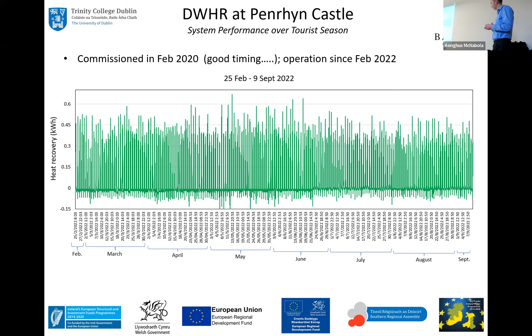Even at nighttime and weekends, when there isn't heat to be recovered, that water is still circulating around, so we're actually losing some of the heat in some of those cases. An improvement of the system in future would be to have some kind of a smart on-off system for that little pump. I'll show you that when we go there later on. But it didn't lose us too much.